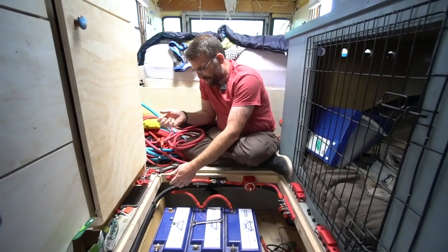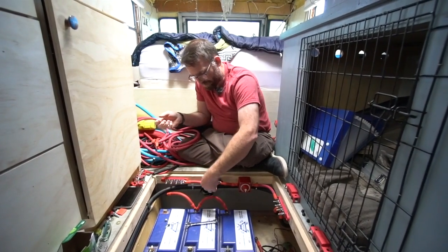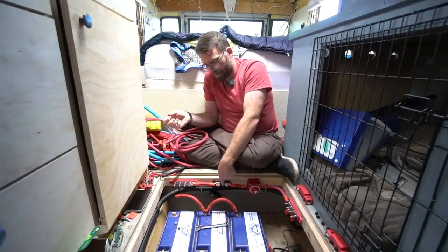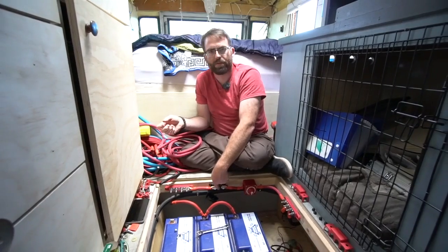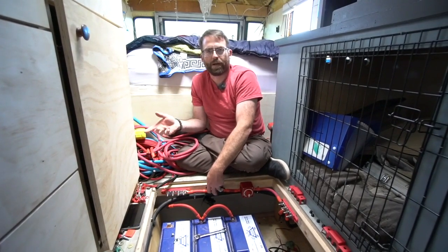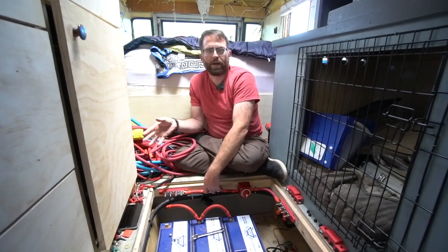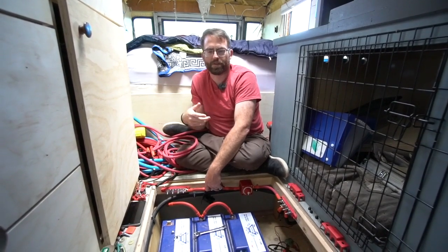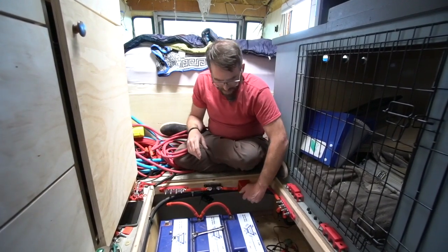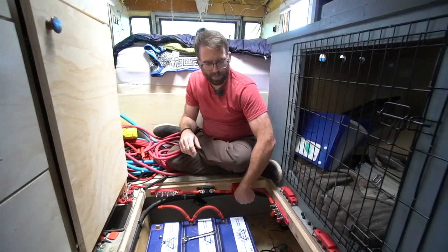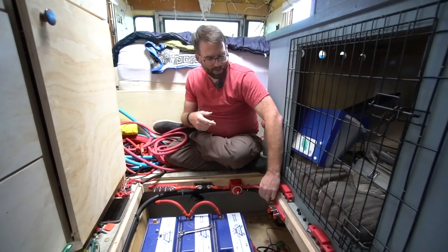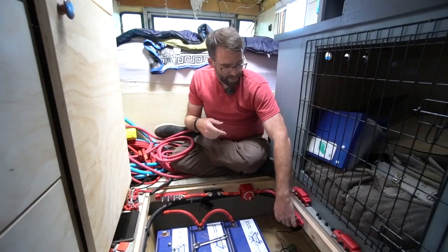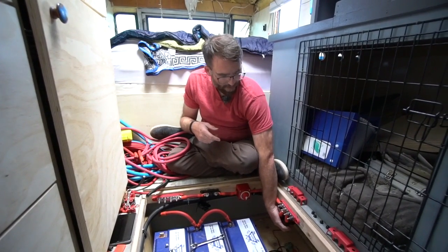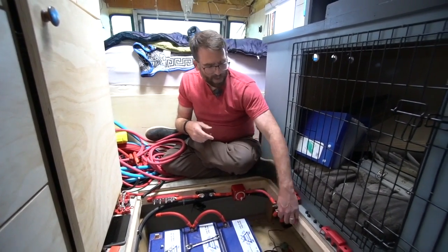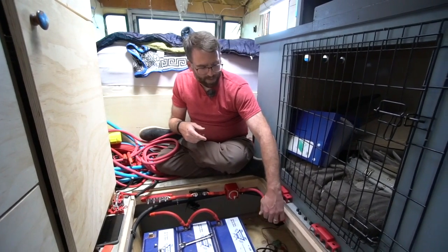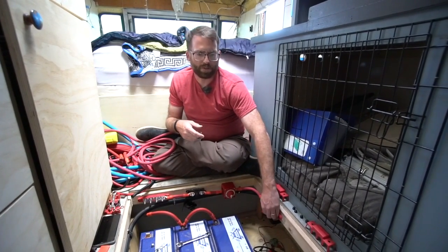The idea then is that we have on the positive side a large system fuse, protection fuse. This is a 250 amp fuse. That gives us about 3,000 watts of power available at the inverter side, if you can compute that back. We have a big shutoff here, so we can just turn off everything upstream of it, and that follows around to this bus side here, and the bus has two cables for the inverter, and then there'll be some smaller cabling for the solar charge controllers here.